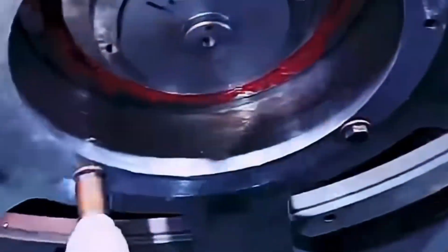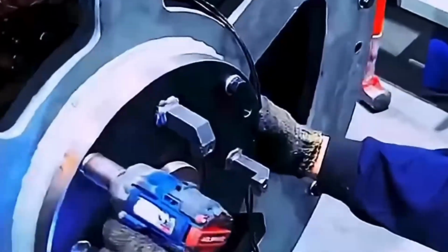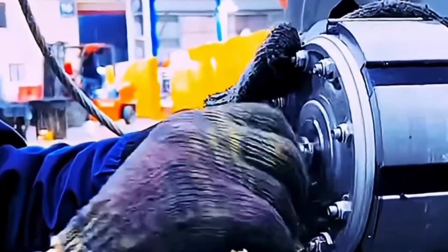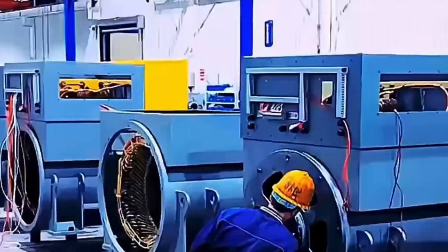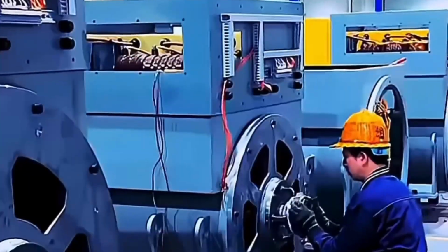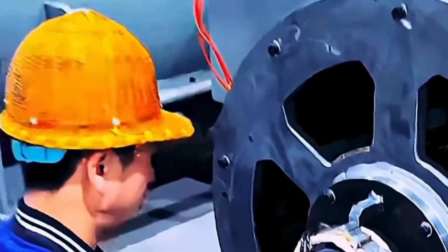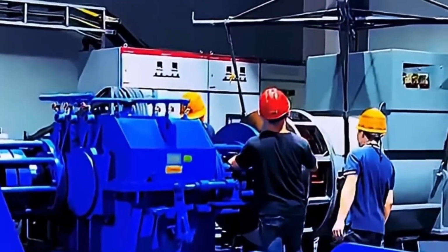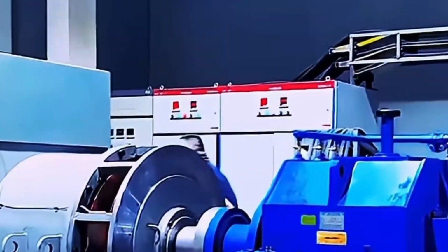Once assembly is complete, the alternator undergoes a factory trial to verify its performance and reliability. The machine is gradually brought up to operating speed, while key parameters like voltage, current, temperature, and vibration are closely monitored. Load tests are performed to ensure stable output under real working conditions. Only after passing all quality checks is the alternator approved for delivery and installation.